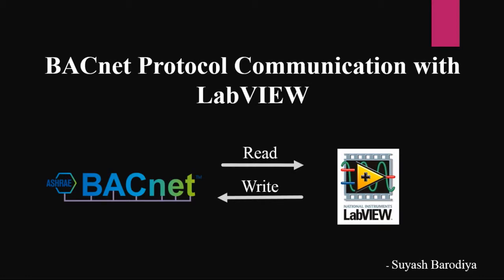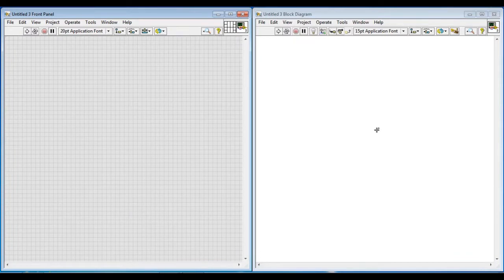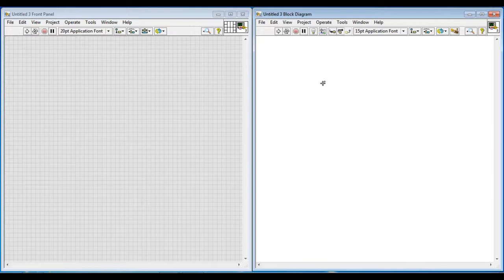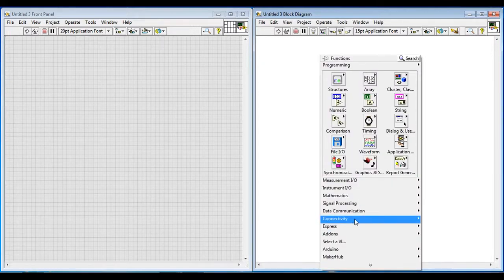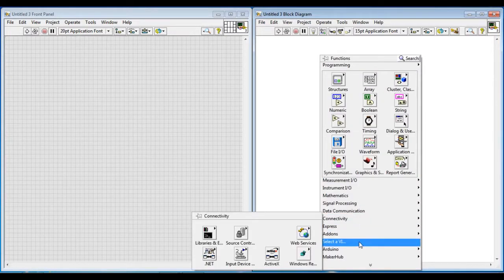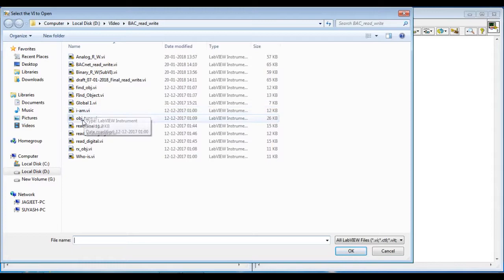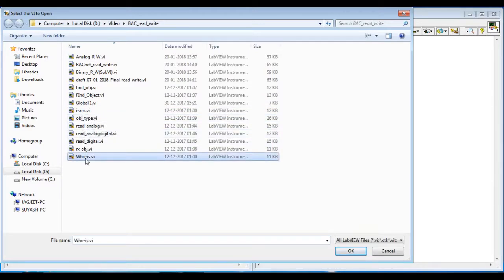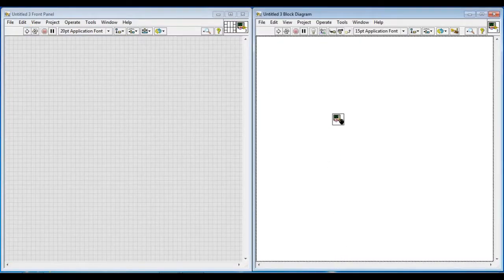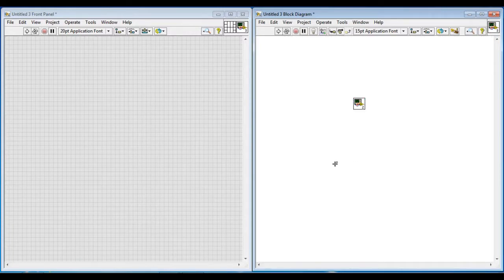To begin with the actual topics, let's open up the LabVIEW software. This is our LabVIEW VI which I have split into two parts: front panel and block diagram. To start the communication with the BACnet device, the WhoIs command must be broadcast. The WhoIs service is used by a BACnet user to determine the device object identifier and network addresses, and some other properties of devices which share the same internetwork.